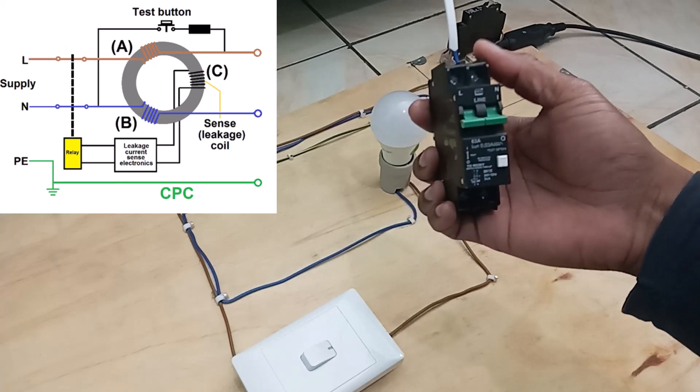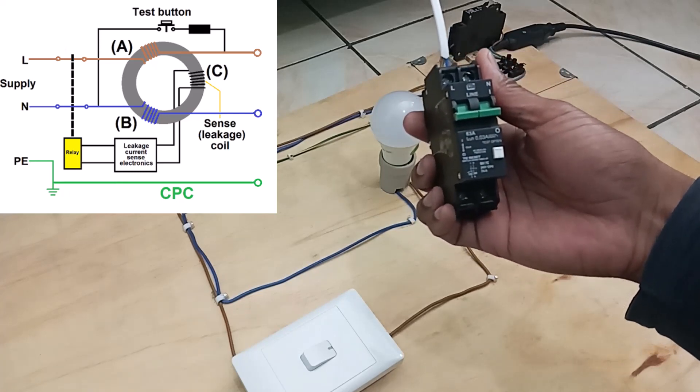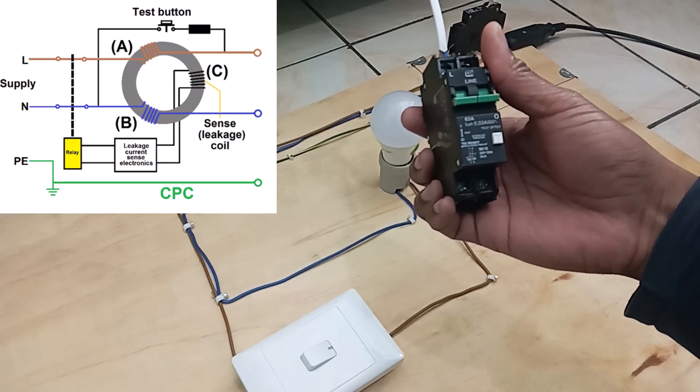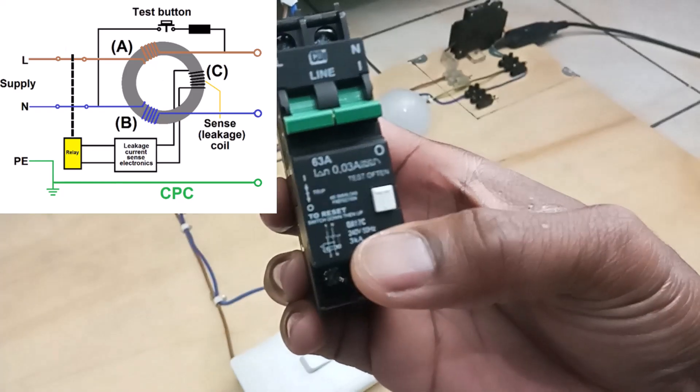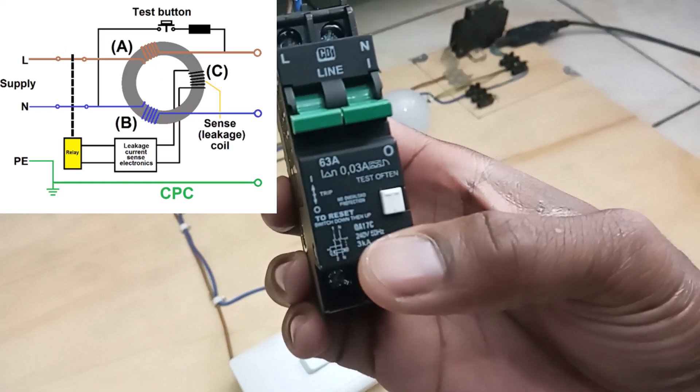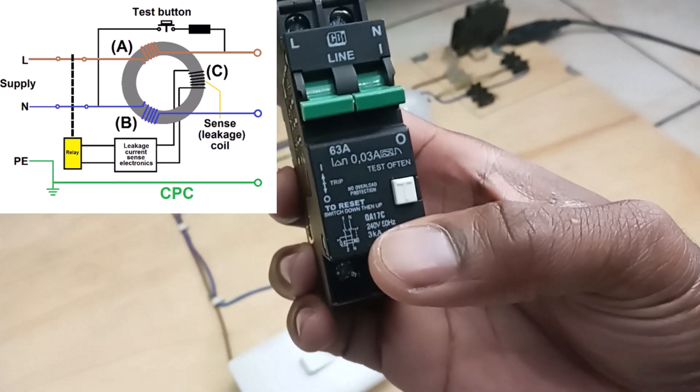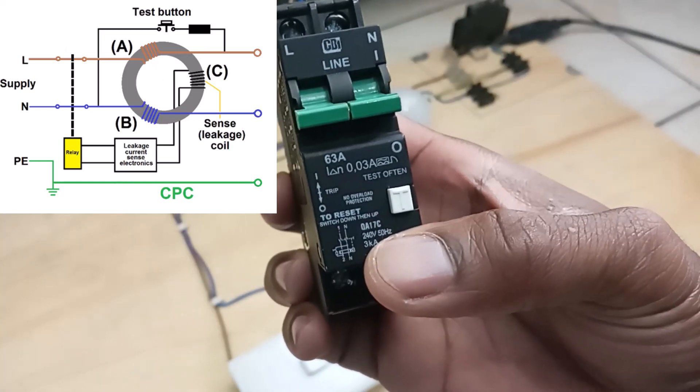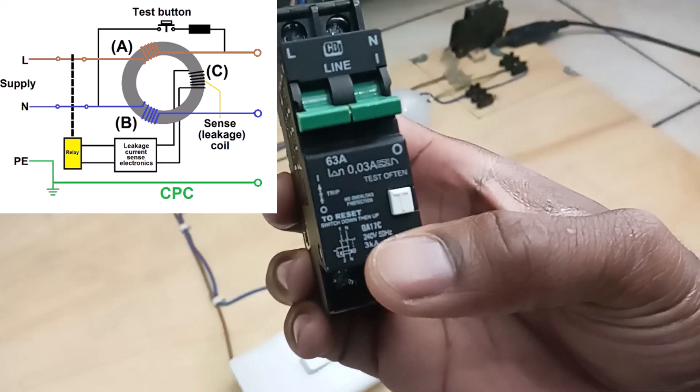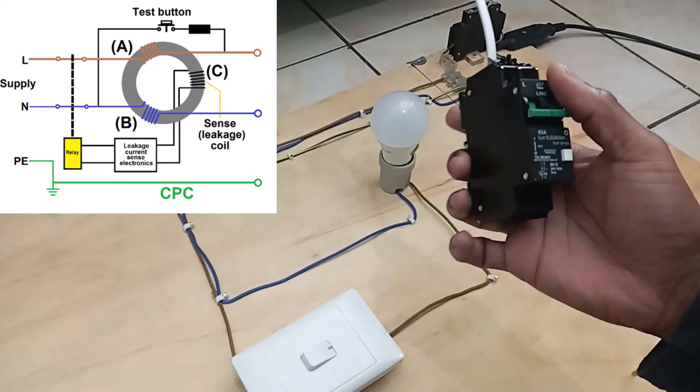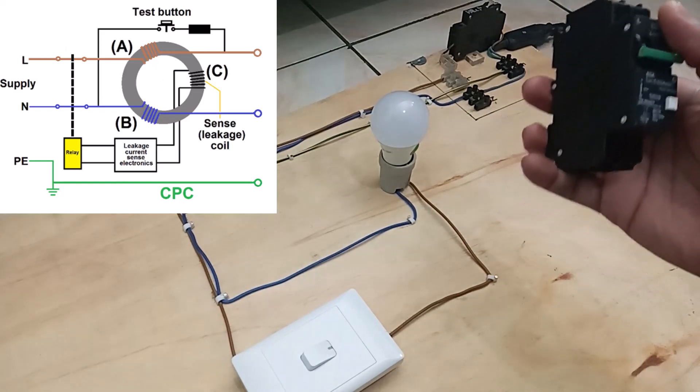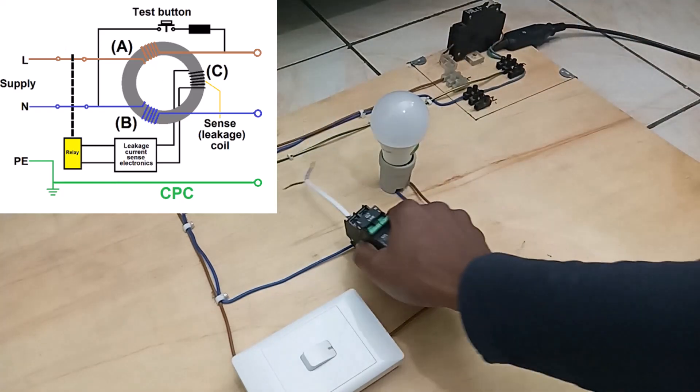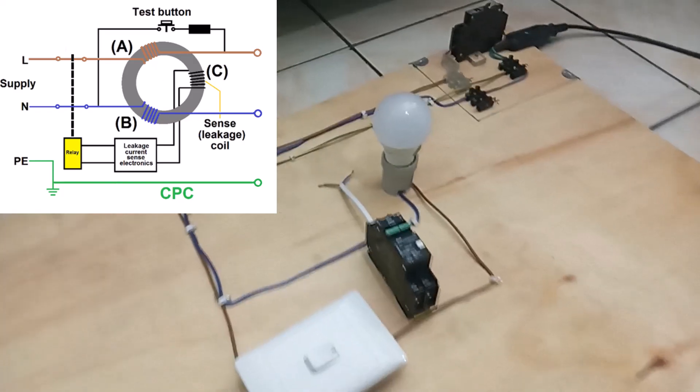This unit won't tell you exactly how much is leaking, but based on the settings that you can set to it, as you can see there, this leakage circuit breaker will trip when the current leaking out of the circuit is equal or greater than 30 milliamps. Now, that 30 milliamps is very big. It's a lot of current that can cause a lot of harm into a human heart.